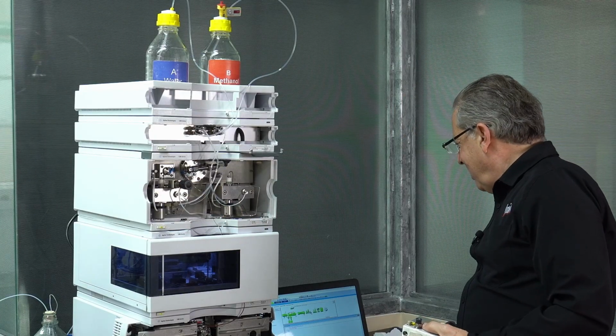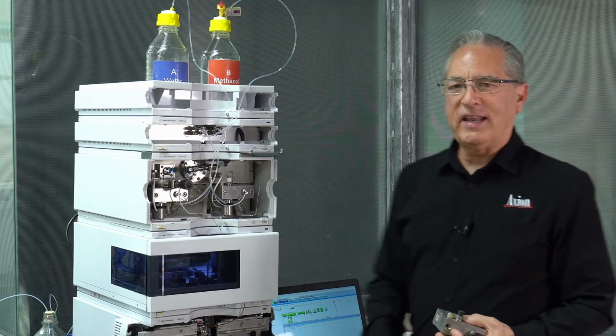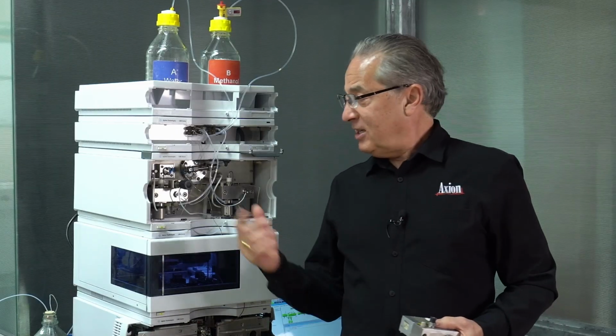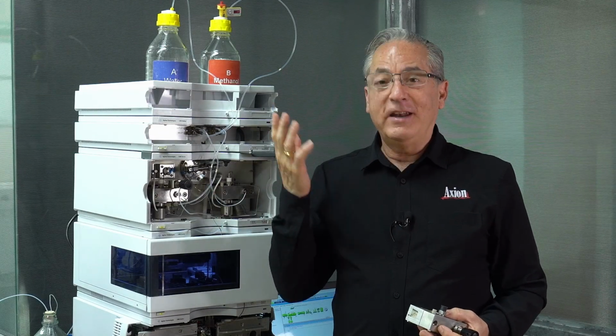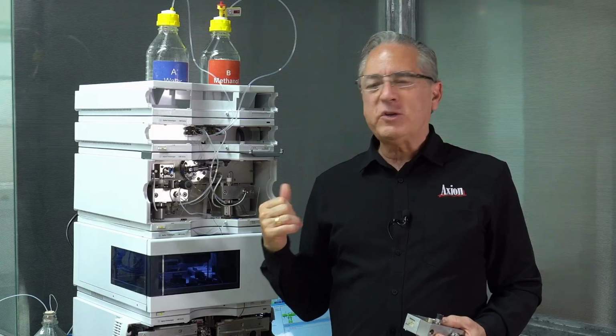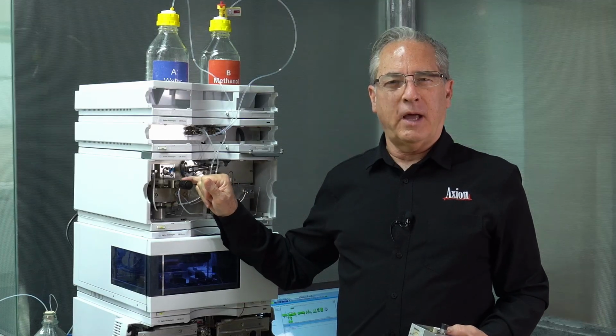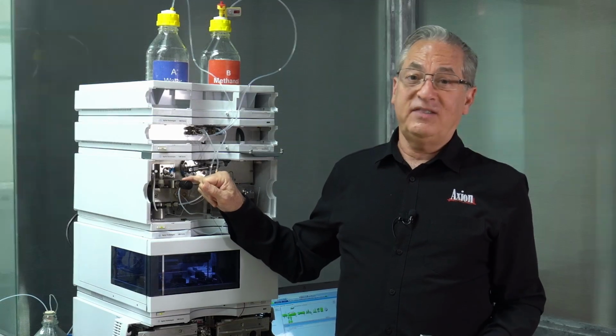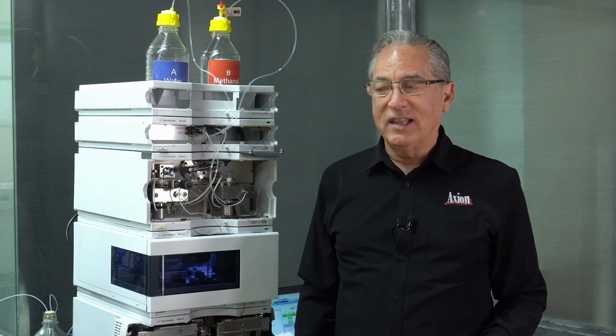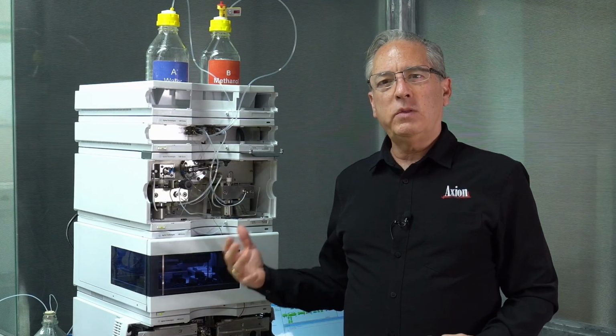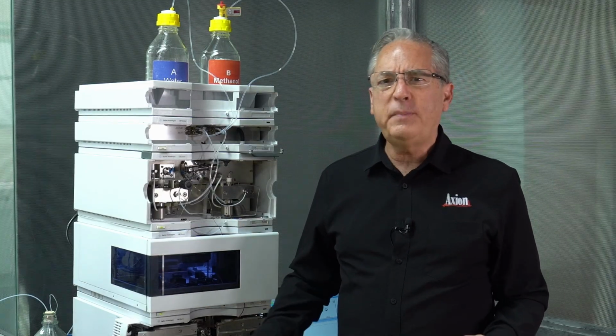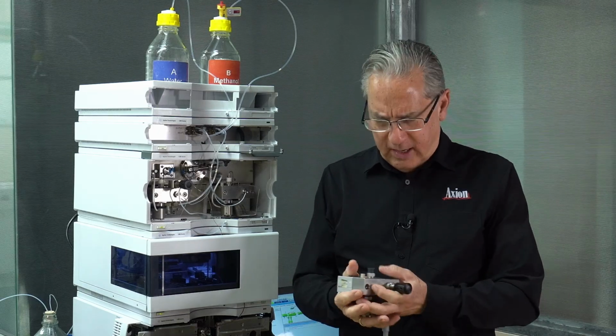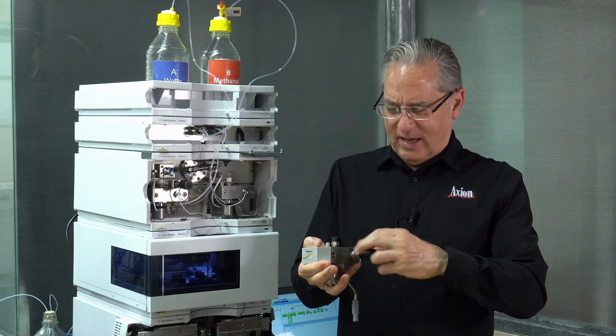In real life, mine is at 10 bar. So there's some resistance in there. I didn't expect this, but there's some resistance in there, which means there's a filter inside here that's plugged up. Now, it's not terribly plugged. I've seen them go up to 400 bar and literally shut down an instrument. So this one is 10 bar, what's that, 150 PSI. My pump's working a little harder than it needs to. So let me show you where that filter is.